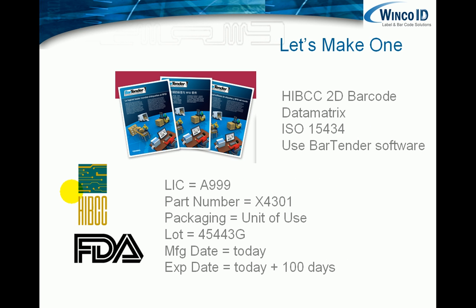So we're going to actually make one using BarTender. We're going to make an HIBCC 2D barcode using the data matrix barcode format, and we're going to encode it to ISO 15434. And just for the variable data that goes into our barcode, our LIC code is going to be A999. We've given our item a part number. The packaging level, and I'll talk about that a little bit as we actually go through the design. It's going to be unit of use, or just one item per package.